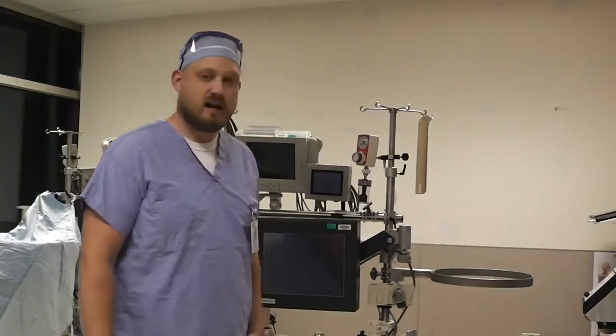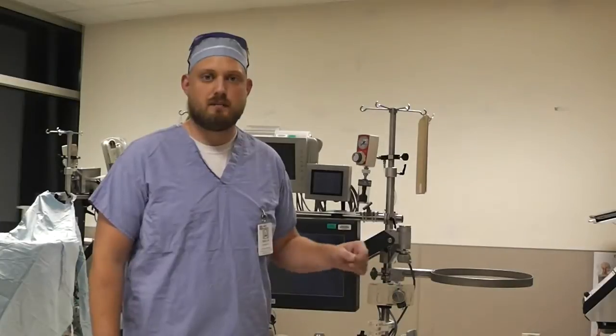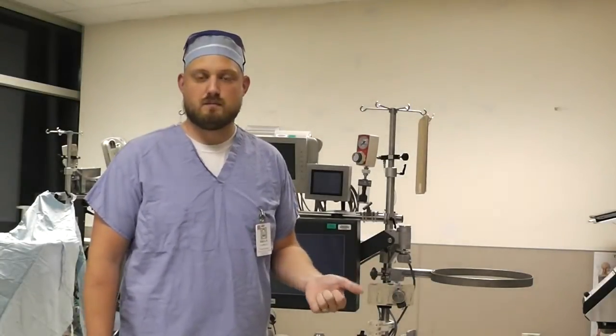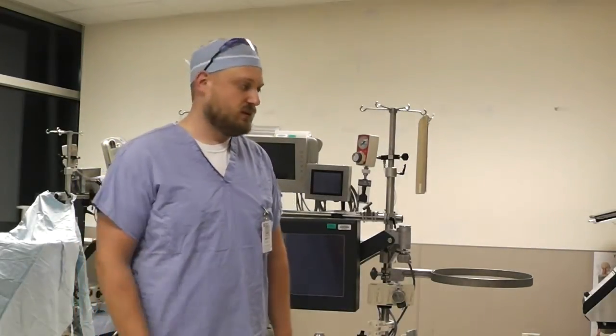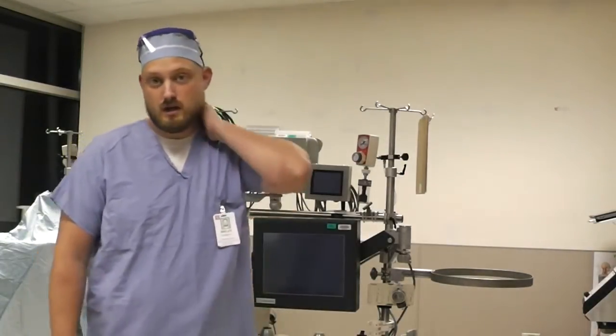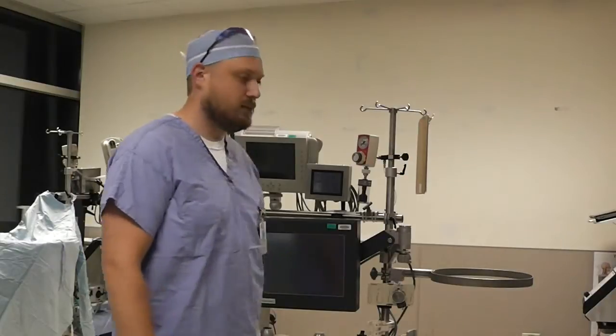Now, I don't know what your time is going to be. We had a time of 35 minutes to set up the pump, prime it, get it into the room, and perform the various procedures in the room to get ready to go on pump. But that was with the old RX-25 oxygenator, which was actually a considerably more complicated setup than the new FX-25 setup that we have now. So I know they have plans to shave that time, but it will still be a similar deal. So I'm going to start with a bare pump and show you guys how to set that up.